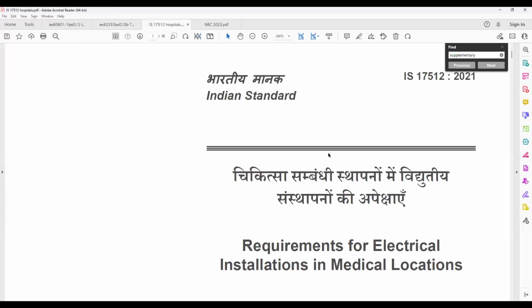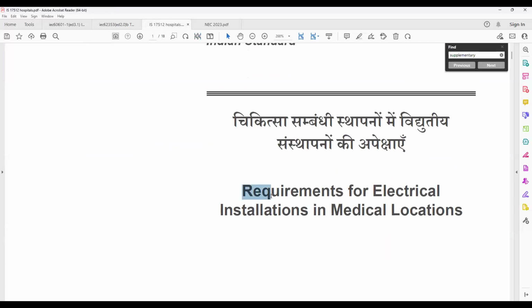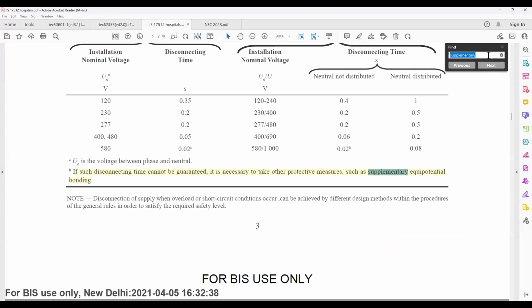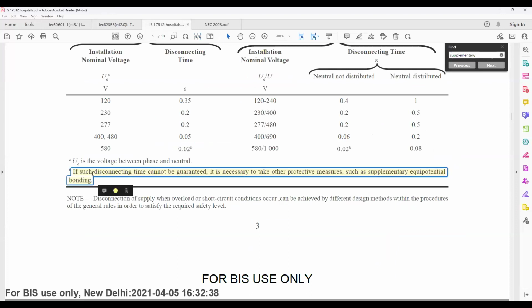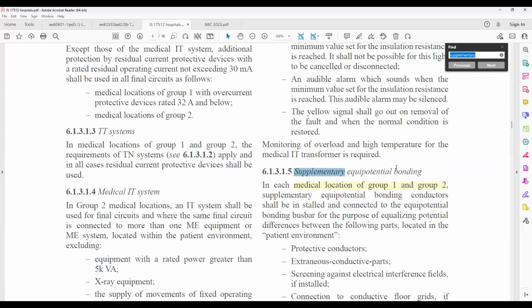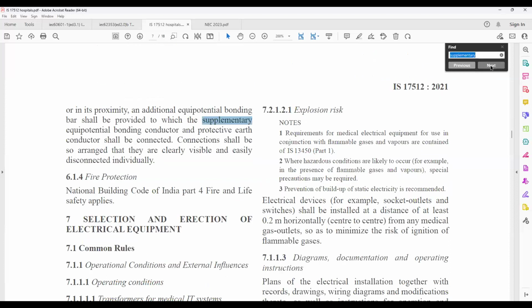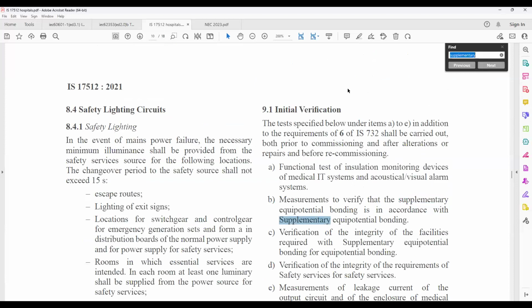Similarly, the other Indian standard, for example IS 17512, which is a very new standard, but of course the old version was also there. Requirement of electrical installation in medical location. The first two standards which I have shown are for the equipment, whereas here is a location where you are using that particular equipment. For example, I'm searching the term supplementary. What is written? If such disconnection time cannot be guaranteed, that means you are sure that the MCB or the protective device is unable to trip under certain conditions, it is necessary to take other protective measures such as supplementary equipotential bonding. You have to bond all the metal parts in the building. Like this, several safety measures are recommended in the standard.